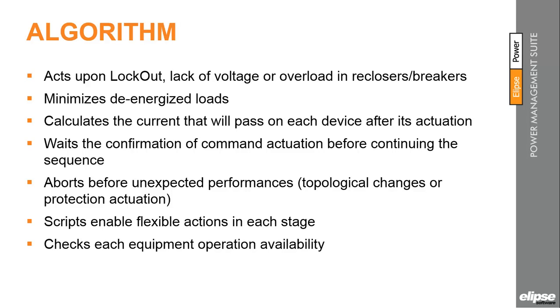If any unexpected performance is identified, it aborts the procedure and waits for the maintenance teams to resolve the problem. That could be any topological changes or protection actuation. This is more of a conservative policy for the solution actuation. Another point is that the scripts enable flexible actions in each stage. For each state value of the switch device, open or closed, a protection profile is set in order to keep the protection system running accordingly. So a comparison is made between the configured and the field value to decide which is the appropriate profile.